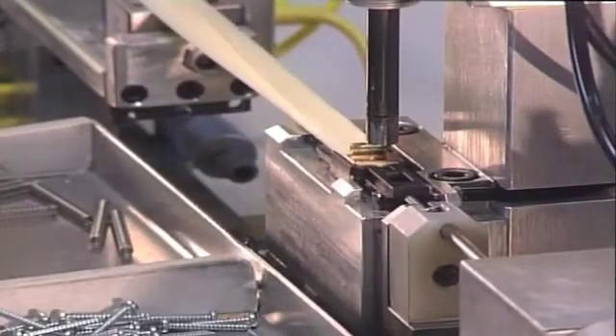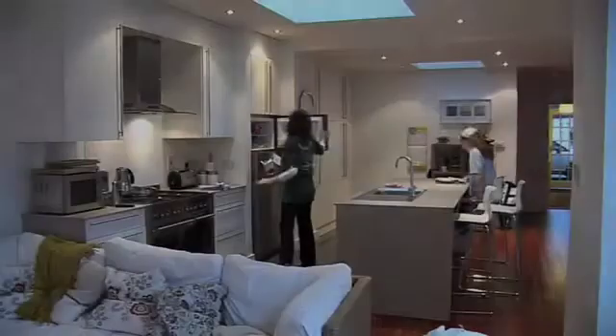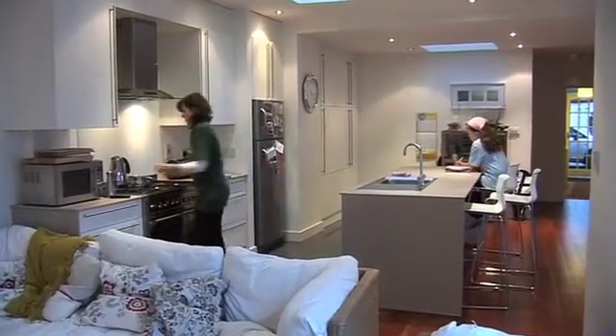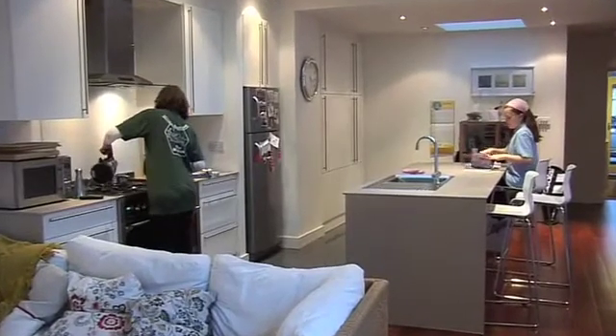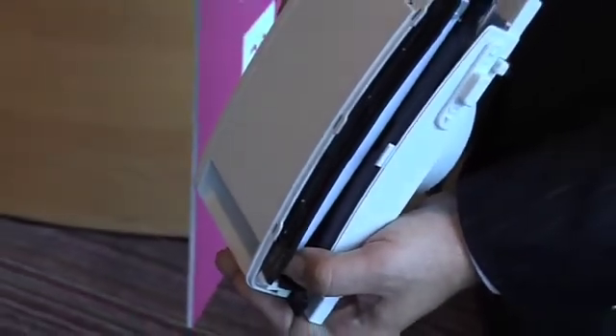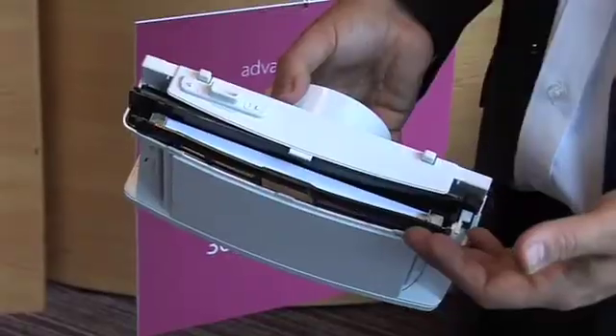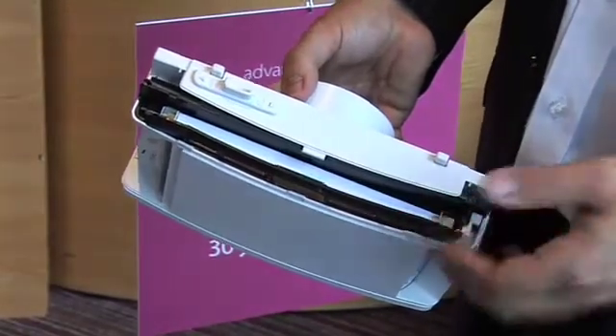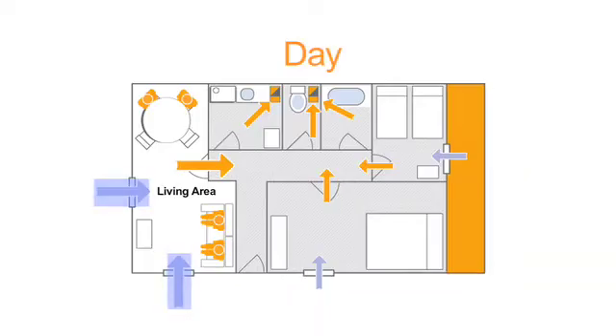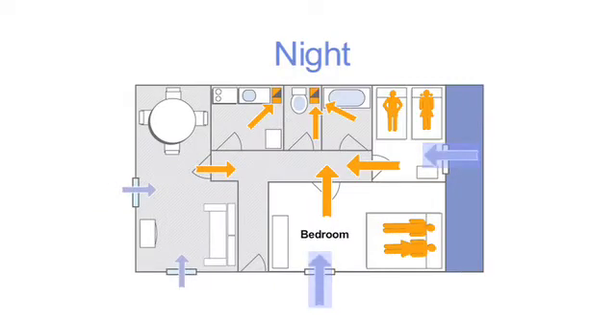So what is DCV? Almost everything we do in our homes, such as cooking, cleaning, washing and even breathing, produces humidity and therefore affects indoor air quality. This is why the humidity strip is at the core of what we do. As humidity rises and falls in the room or building, this humidity sensitive strip is able to open and shut grills accordingly and control indoor air quality. It enables us to simply and effectively control the volume and movement of air into and out of rooms based on actual need.